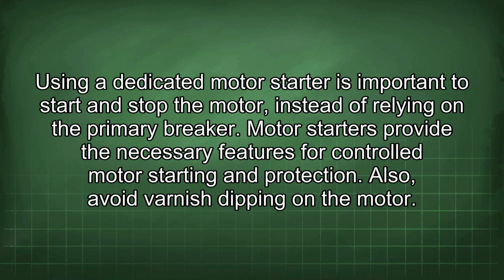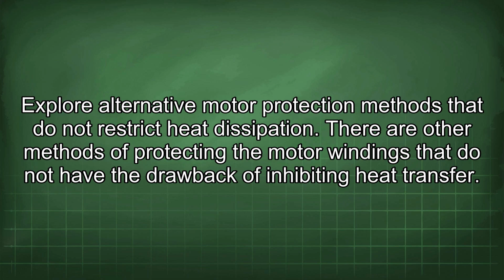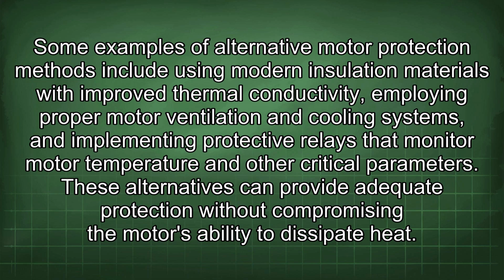Also, avoid varnish dipping on the motor. Explore alternative motor protection methods that do not restrict heat dissipation. There are other methods of protecting the motor windings that do not have the drawback of inhibiting heat transfer. Some examples include using modern insulation materials with improved thermal conductivity, employing proper motor ventilation and cooling systems, and implementing protective relays that monitor motor temperature and other critical parameters. These alternatives can provide adequate protection without compromising the motor's ability to dissipate heat.